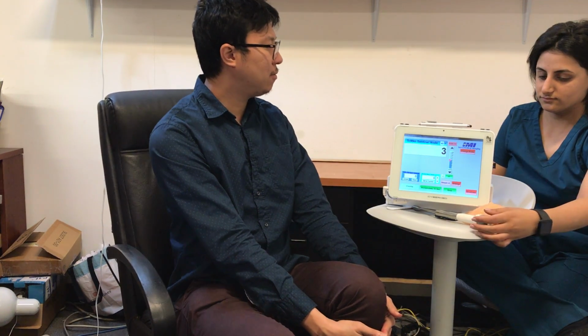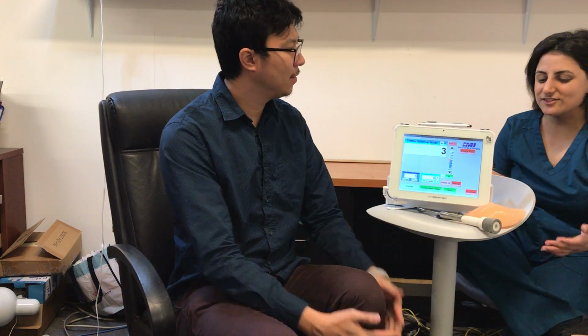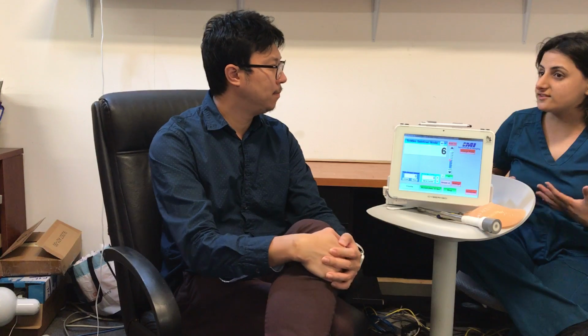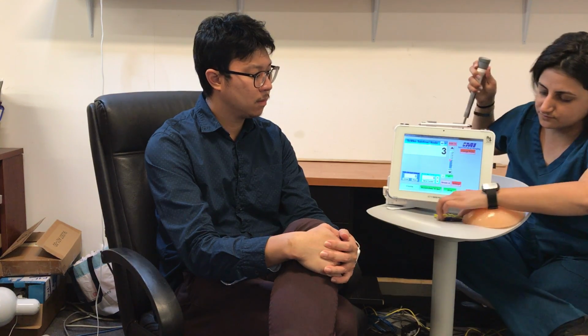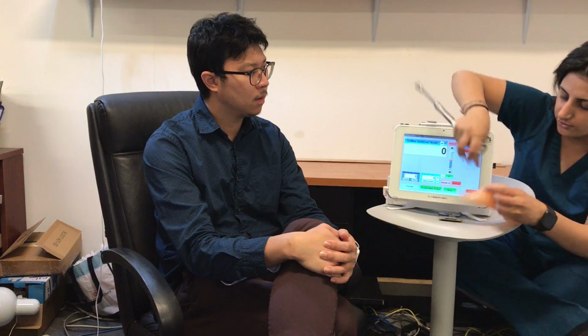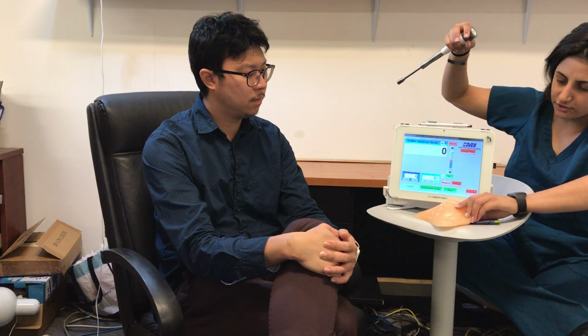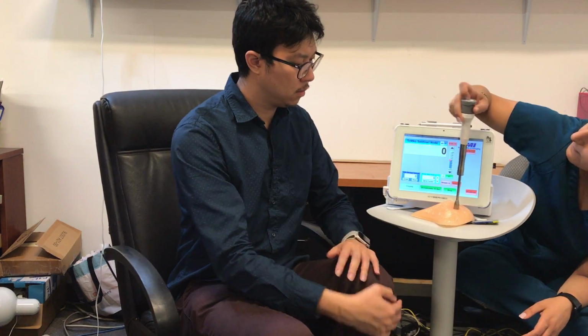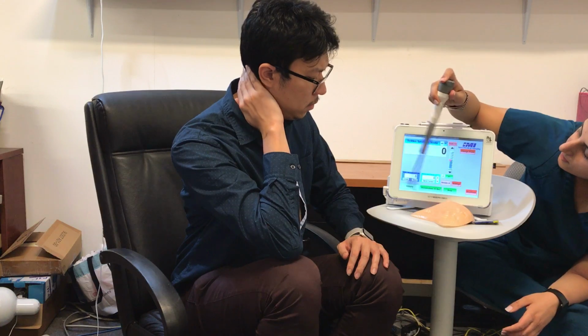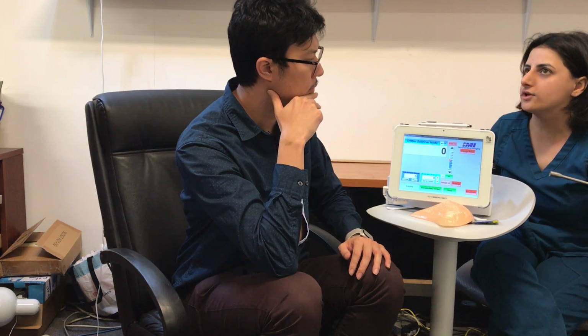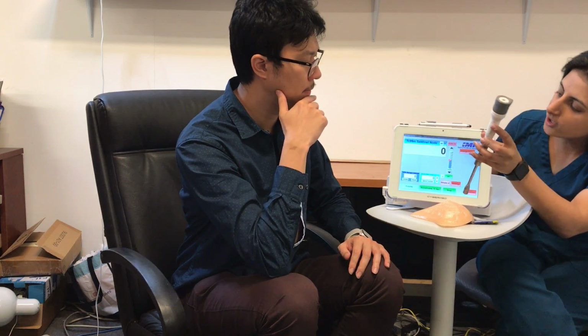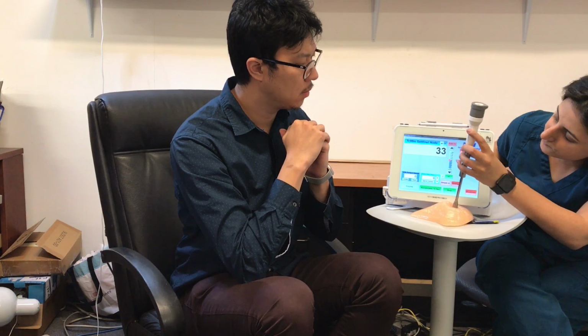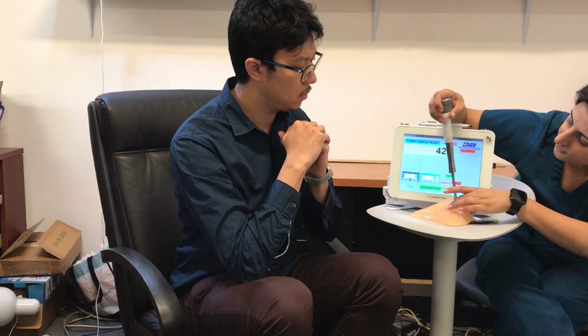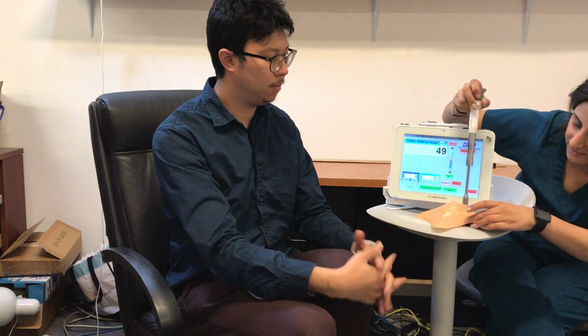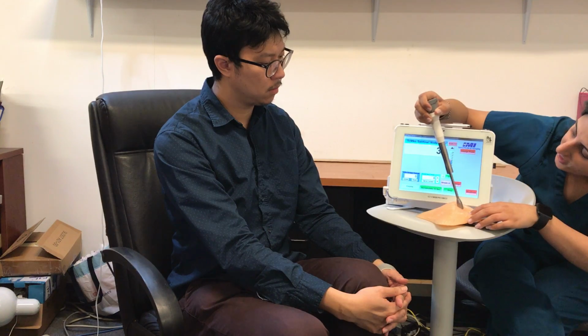So what makes your product stand out from the other gamma probes on the market? Yes, as I mentioned, we have the highest sensitivity on the market. So by having a higher sensitivity, we are able to find more sentinel nodes, if there are more sentinel nodes. So if you had a node deeper in the tissue, let's say you had a thicker piece of axilla, and with another probe, you would get a lower amount of count, so you would maybe get a false negative with a different probe. But here, you could be led to getting some kind of count, and your surgeon would actually want to go a little bit deeper here, and think, okay, maybe there is something going on here. There is a jump. I should actually make a cut.